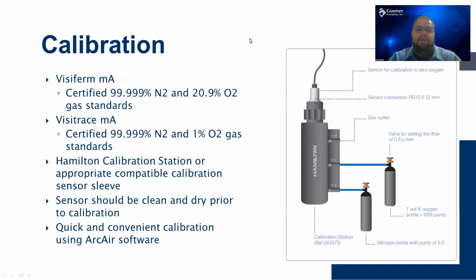For the low point, we really recommend 99.999% N2, or it's called 5 nines. That percentage provides the ideal amount of low oxygen in your environment. So if you were to use 99.9% CO2, which is the common grade for food grade CO2, with the 3 nines you could have enough oxygen in there to throw off the low point for calibration. So the 5 nines ensures that the oxygen level in that nitrogen is so low that you'll have a good low point calibration. For the Visitrace mA, again, 99.999% nitrogen. And then at the high end, you'll have a 1% oxygen gas standard.